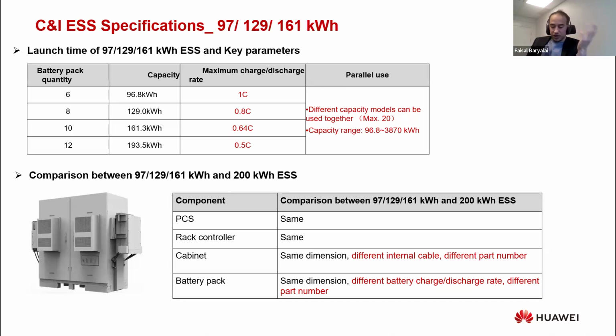One more thing - even though these batteries are exactly identical in hardware, especially the first 3 capacities, we cannot add more modules later just to increase capacity at the moment, because each cabinet is pre-programmed for a specific amount of modules. If it's 6 modules, it's programmed for 6, if it's 8, for 8. But we are in discussion with Huawei about the possibility of increasing the amount of modules in the future.